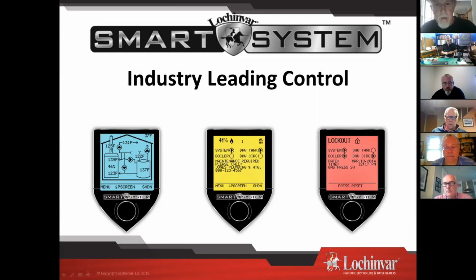And then the red lockout screen. Red lockout screen, something requires immediate attention. The boiler is in alarm and it is not firing. And it will alternate between what the lockout is and your company's name and phone number right down here at the bottom. Real important, we get a substantial amount of calls from people. My boiler's locked out, I've got no heat. Hey, what are you locked out on? Well, I'm locked out on lockout. And that is the way the screen's going to read at the top, but go right down here, and that's going to tell you what the lockout itself is, okay?